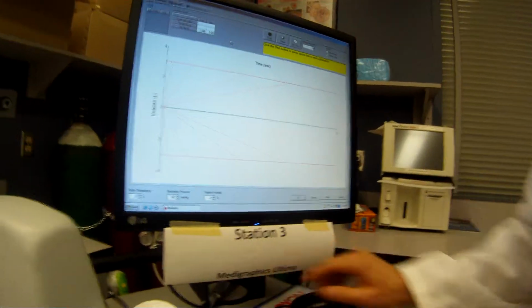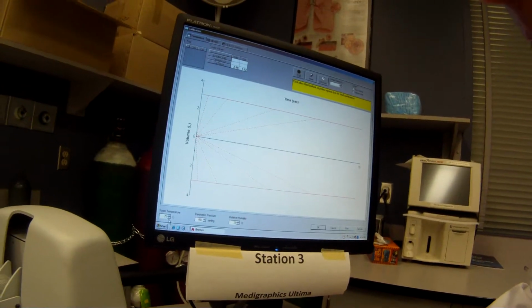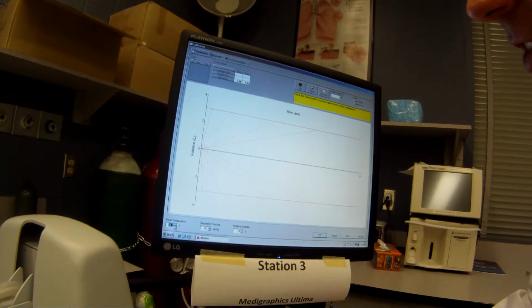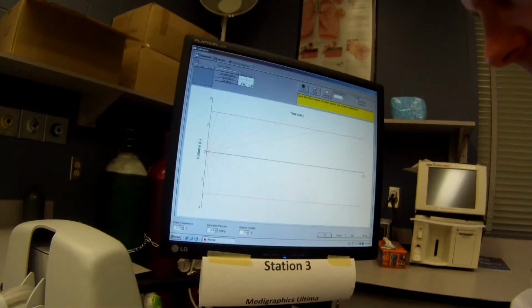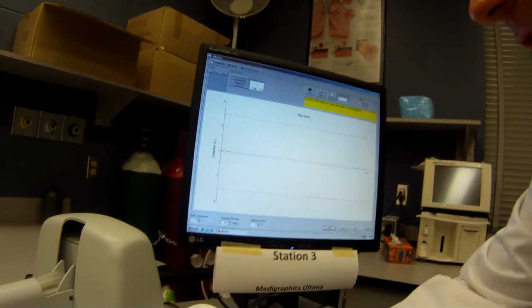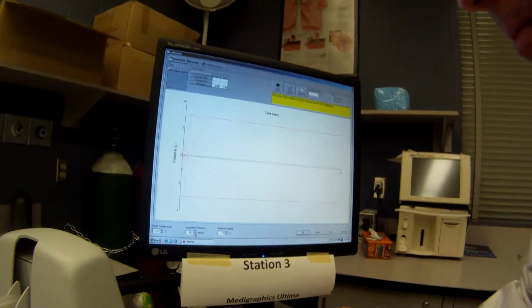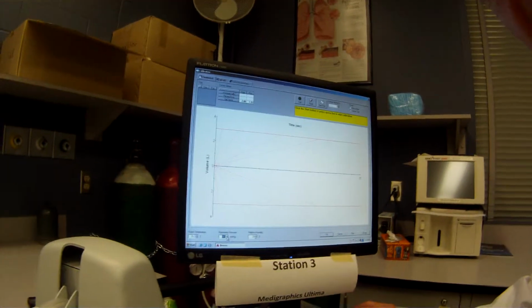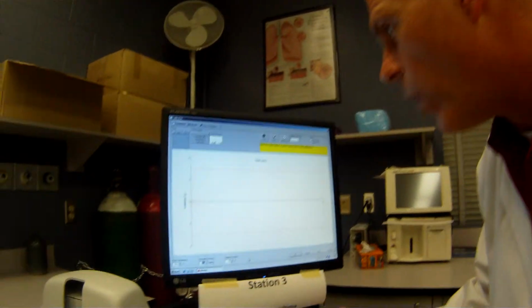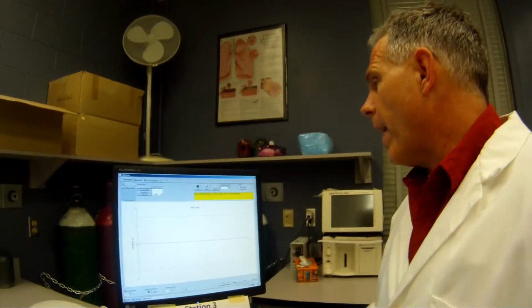We have to make sure we've got the temperature set properly for the room. So right now it's 23 degrees. I'm just going to set that back in here. It's 23.2 degrees. The barometric pressure today is 663, and the humidity is about 29%. So make sure you get those values and set those up right away.